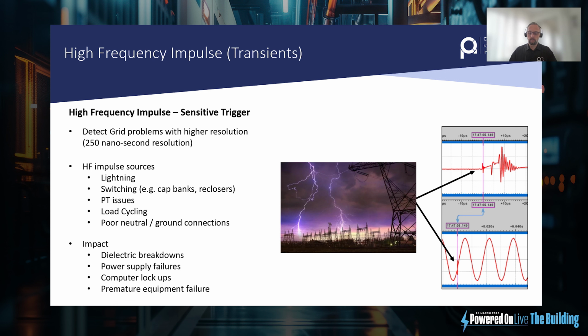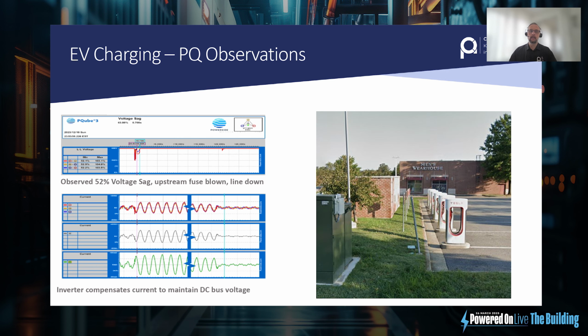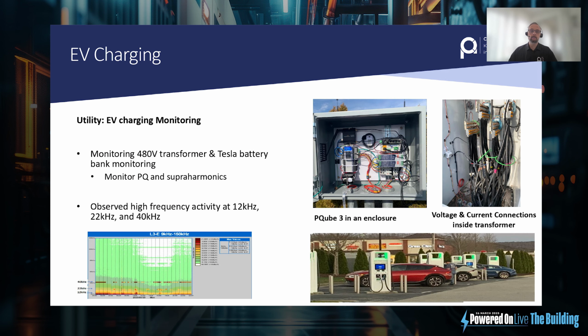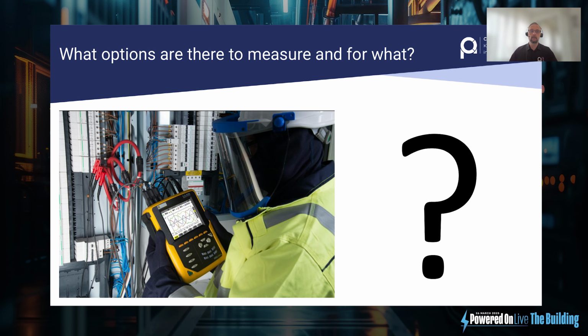Again, if you've got external things like lightning strikes and other things, to be able to know that that was something and you couldn't prevent it, and why something's happened is critical, really. And the same with the EV chargers. Maybe you can determine that one of your chargers is starting to fail in advance, and then you can get someone out there to go and get it repaired and fixed. Same thing here. This is a prime example where we were able to identify that there was some high frequency noise being caused by the chargers that was interfering with other equipment.